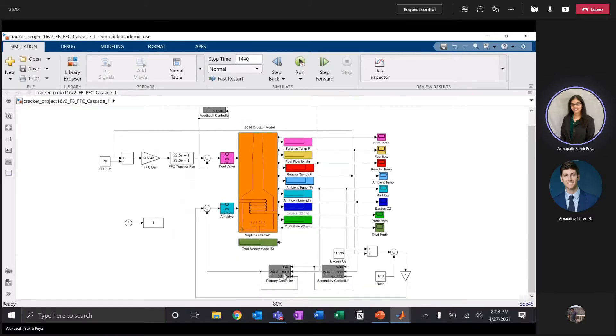Further down, there is a cascade control loop which controls the air valve based on the excess O2 and air flow, followed by a ratio control which also adjusts the air valve based on the flow of fuel and flow of air.